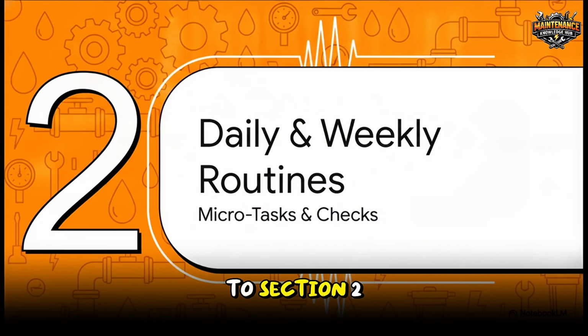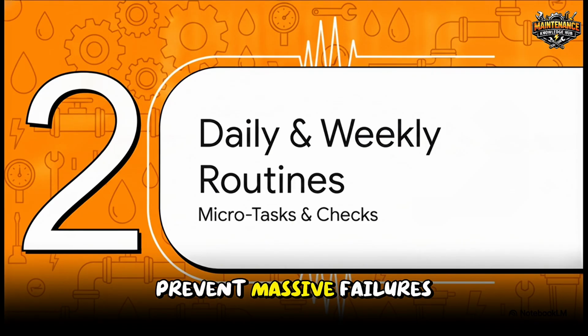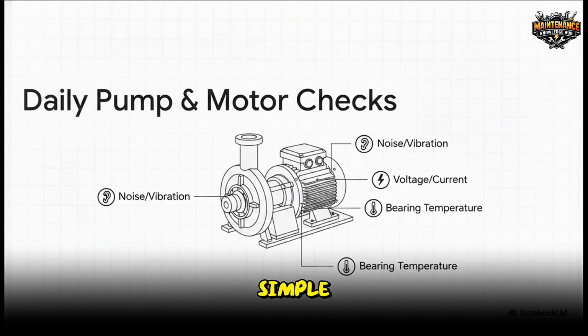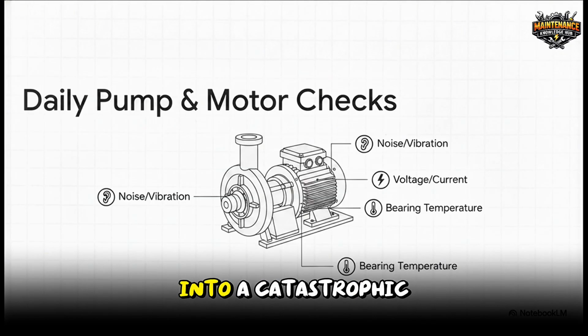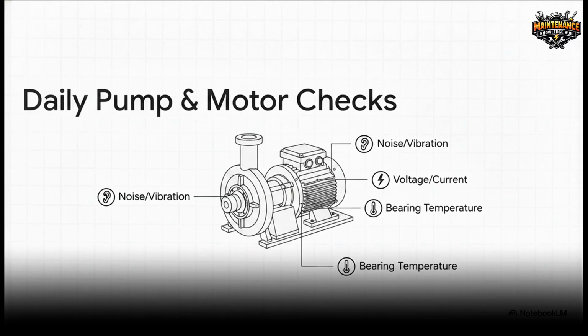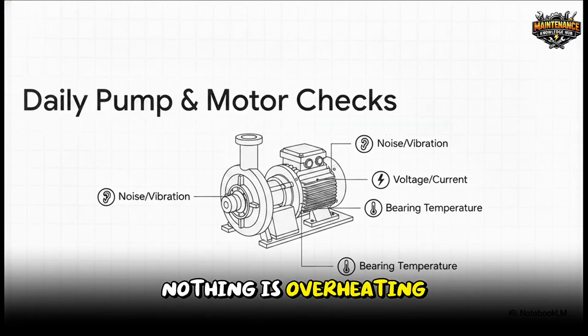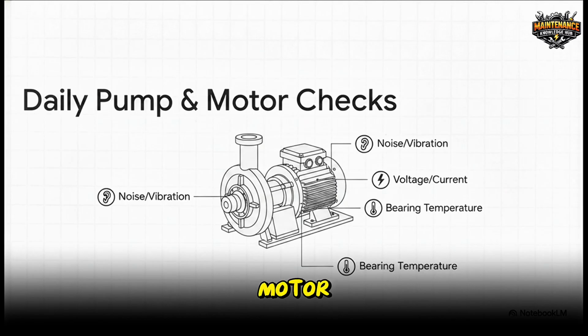Moving right along to Section 2, Daily and Weekly Routines. This is where we see how microtasks prevent massive failures. It's amazing how simple, boots-on-the-ground routines save you so much trouble down the line. For daily pump and motor checks, just actively listening for abnormal noises or keeping an eye on mechanical seals is exactly how you catch a tiny leak before it blows into a catastrophic pump failure. Your team needs to be checking suction and discharge pressures, touching base on bearing temperatures, and verifying motor current and voltage to make sure nothing is overheating. Catching a slight vibration today? That saves you the absolute nightmare of a fried motor tomorrow.